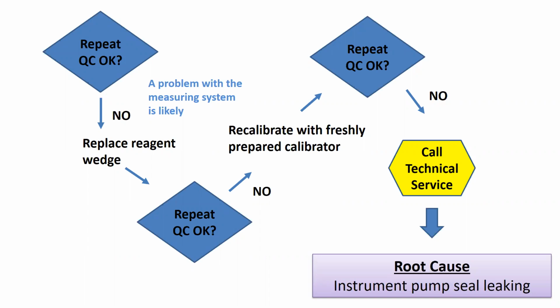The next step we took was replacing the reagent wedge, because we know that an unstable onboard reagent is a frequent cause of QC failure. We replaced the reagent wedge and repeated the QC, but the repeat was still not acceptable. We then recalibrated with a freshly prepared calibrator, repeated the QC again, but this still did not correct the problem.